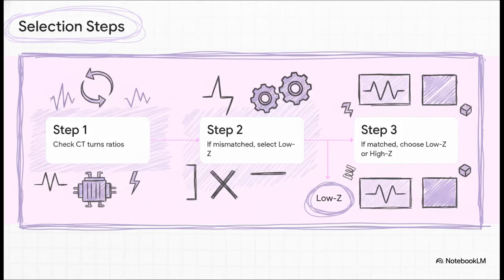Your default decision path should literally always look like this. Step 1. Check those CT turns ratios. Always. If they're mismatched, you go to Step 2, which means you instantly select a low-impedance configuration. Boom. Half your options are eliminated, no debate needed. Only if those ratios match perfectly do you proceed to Step 3, where you finally get the luxury of choosing between software flexibility and hardware stability.